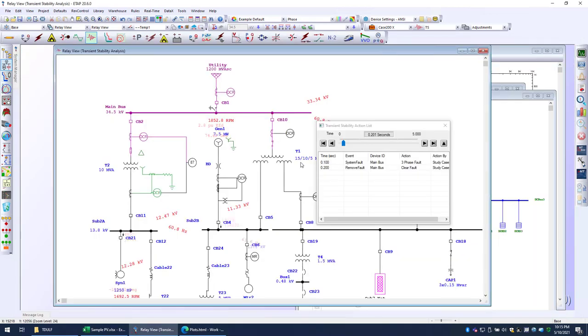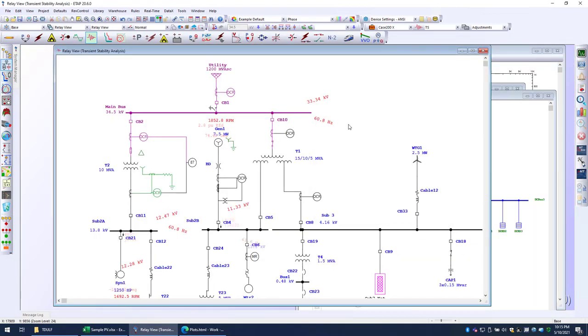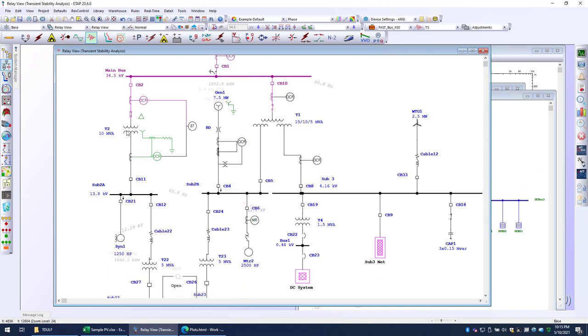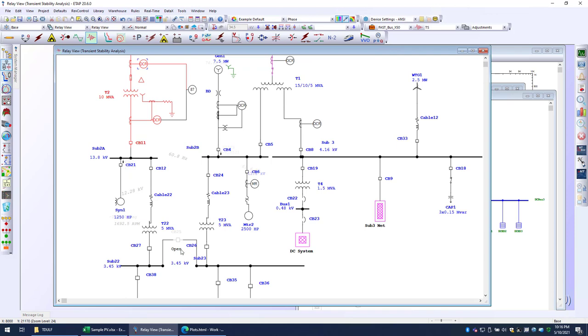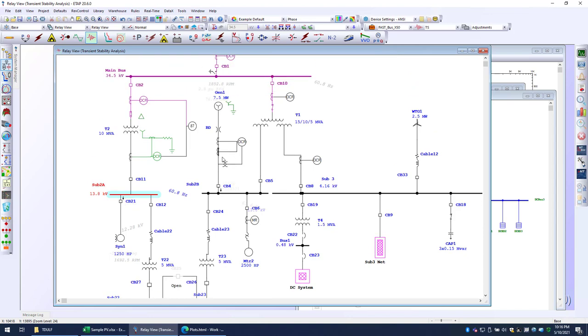I'd like to do one more disturbance, and that is a fast bus transfer in this particular location. So what we're going to do is have a fault in this location, so this transformer is going to be completely isolated. CB2 and CB11 are going to quickly open, and then within 50 milliseconds, we're going to close this tie, and we're going to see what the system stability and the frequency is again on this critical bus sub-2A. Let's go ahead and do that.